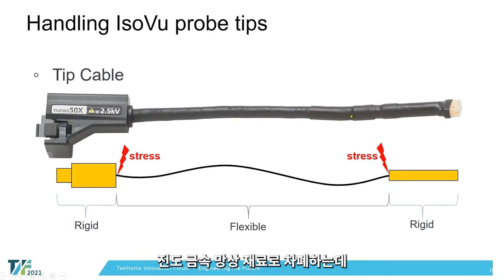So there's a metal enclosure behind the heat shielding here. And in the case of an MMCX tip, that would be a little bit further down the tip range. But the point here is, when applying any particular force upon this tip, that's where most of the strain will come in. And that's important because, to achieve as high a performance in common mode rejection as IsoVu is capable of, we shield the entire cable with a conductive metal mesh material all the way from end to end on this tip.